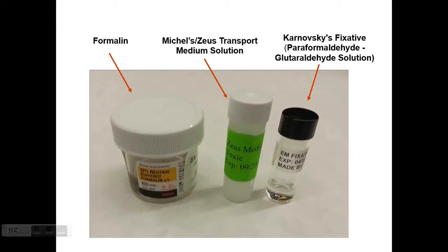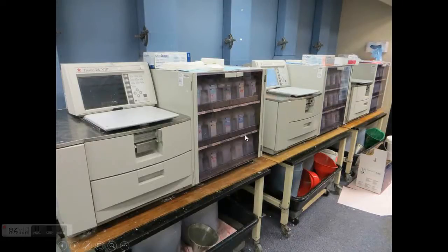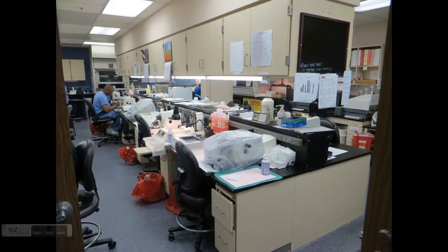For light microscopy, formalin-fixed tissue gets wrapped in tissue paper, put in a tissue bag, and then placed into a cassette. This is sent to processors, and after processing, a technician embeds the tissue into paraffin. Eventually a paraffin block is created that sits on the reverse of the cassette. This processor automates most of the process, but we still need technicians to embed into paraffin and cut sections.